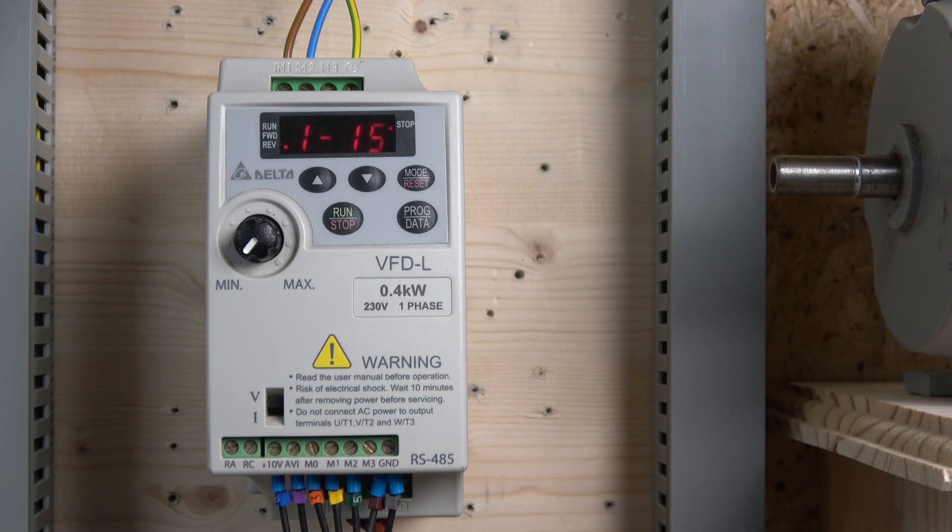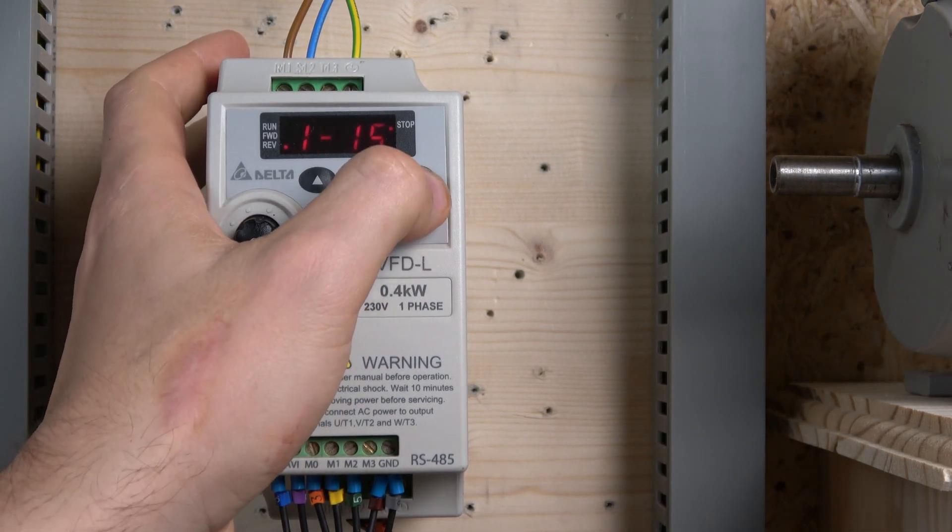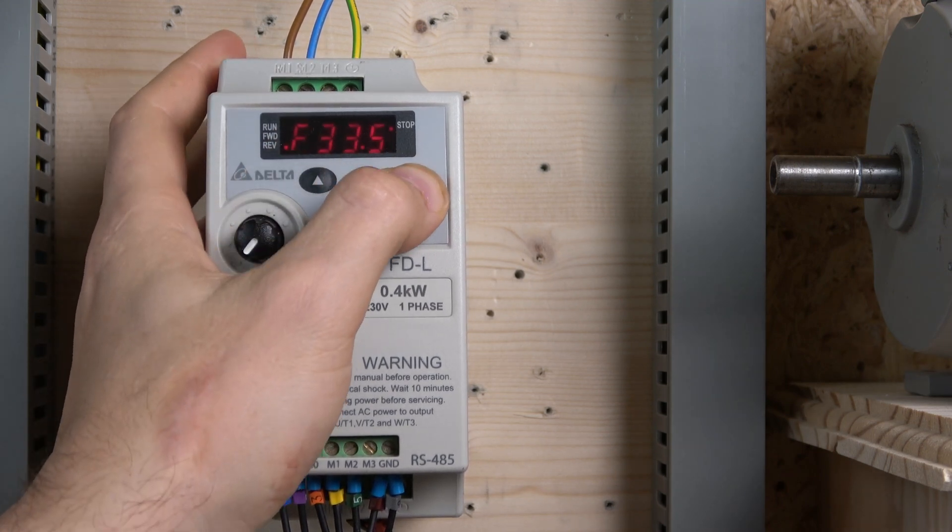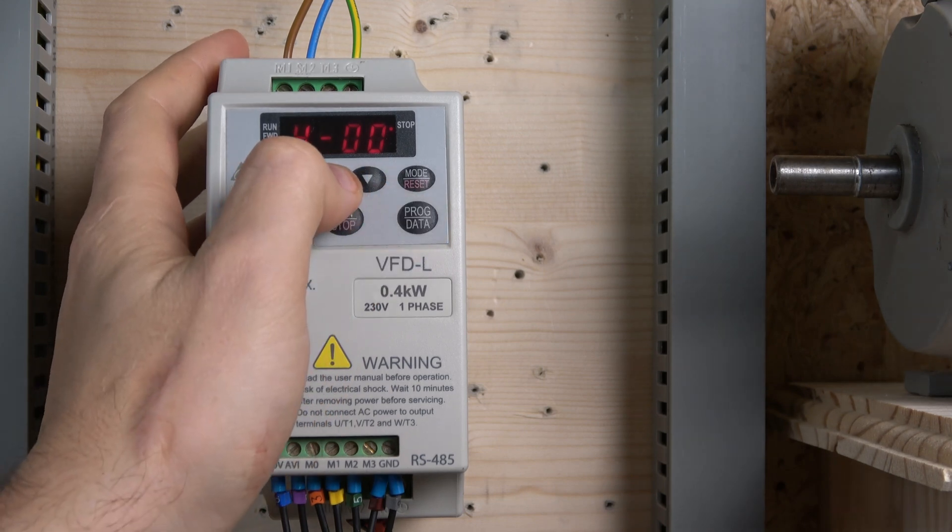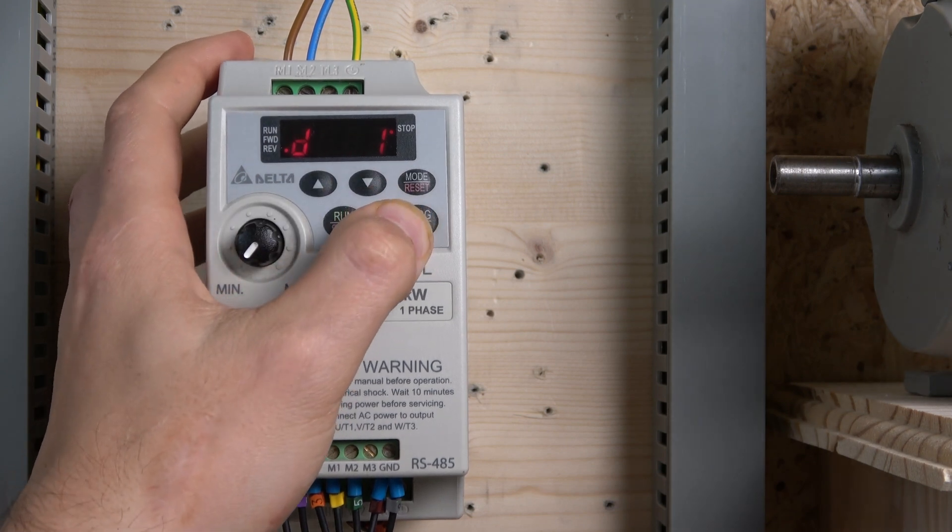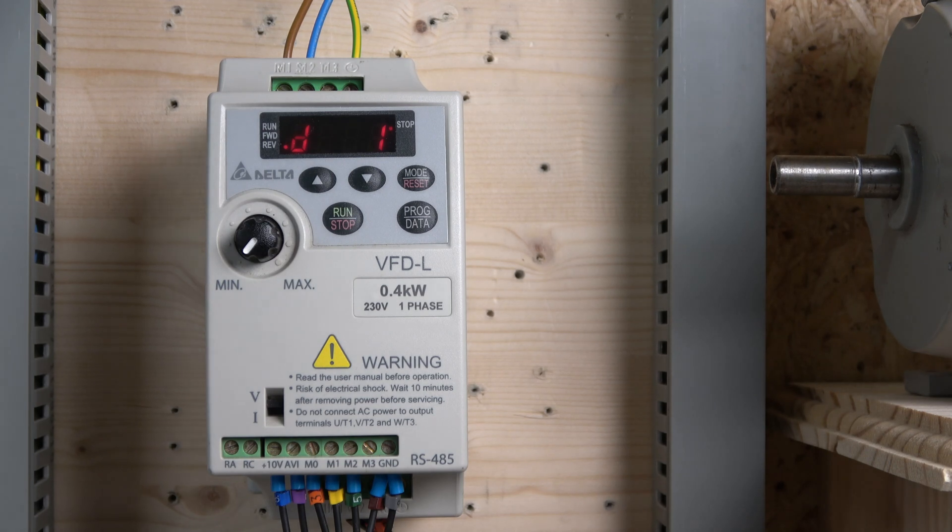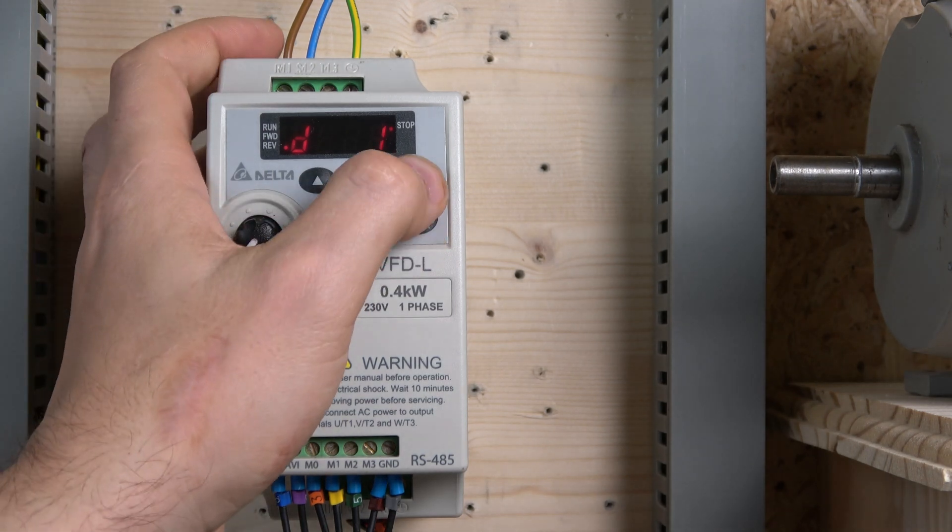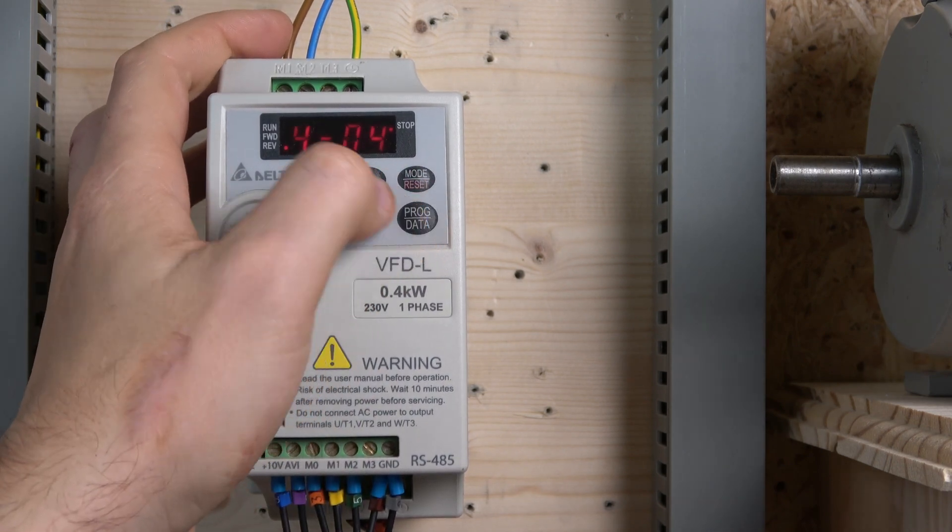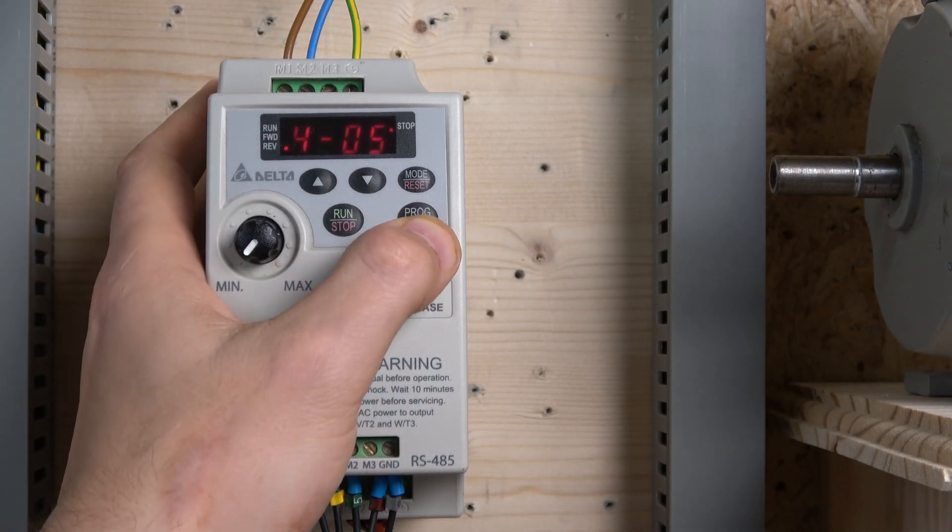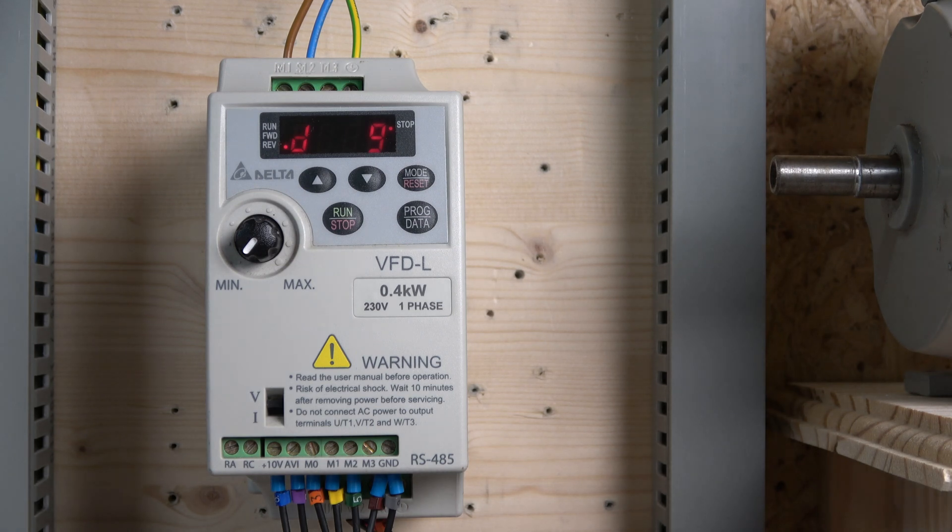From there on we need to set up our IOs. To set up IOs you need to go to parameter group 4. The first one is 4-4, and you change that one to one which will make M0 forward stop and M1 reverse stop. The next one you need to set up is 4-5 which is going to be M2, which is going to be jog operation, which is at number nine. So all our IOs are pretty much set up. This is where the potentiometer comes in, 10 volts and AVI. Let me put the cover on and we'll see how it works.